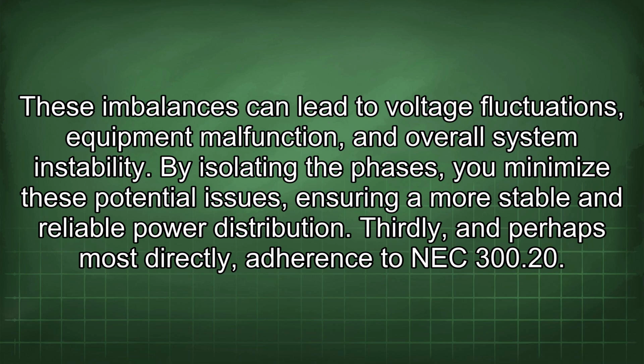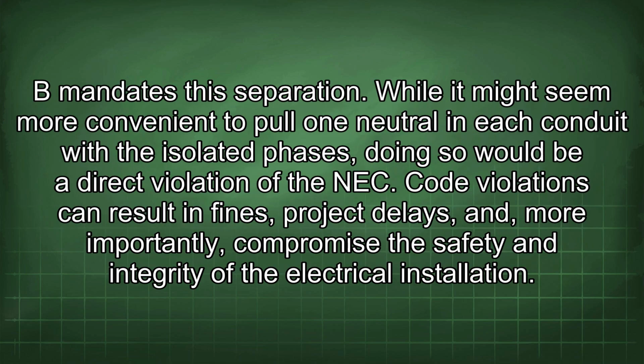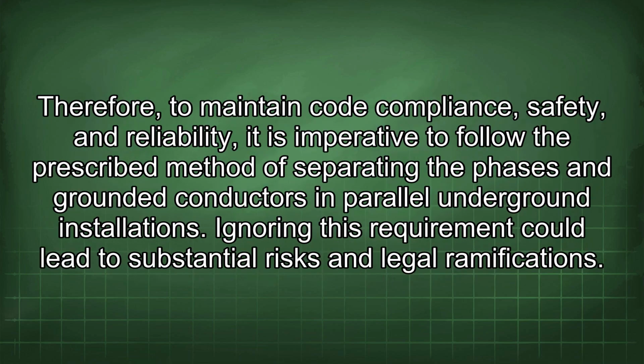Thirdly, and perhaps most directly, adherence to NEC 300.20 mandates the separation. While it might seem more convenient to pull one neutral in each conduit with the isolated phases, doing so would be a direct violation of the NEC. Code violations can result in fines, project delays, and, more importantly, compromise the safety and integrity of the electrical installation. Therefore, to maintain code compliance, safety, and reliability, it is imperative to follow the prescribed method of separating the phases and grounded conductors in parallel underground installations. Ignoring this requirement could lead to substantial risks and legal ramifications.